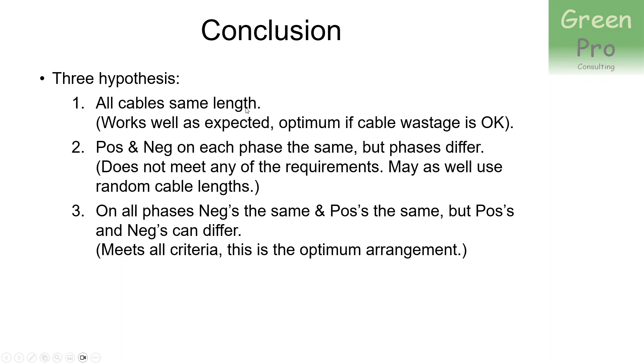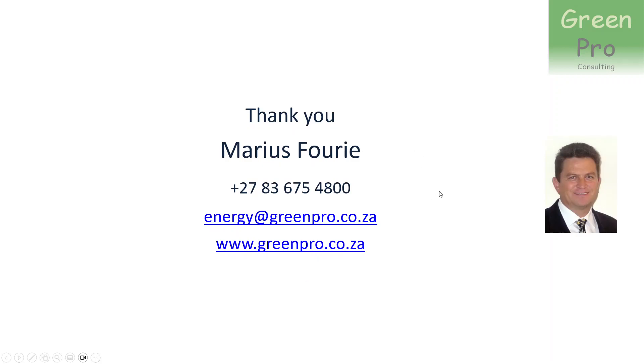In conclusion: all cables the same length works well as expected, but may waste cable and increase losses. Positive and negative the same per phase but phases differing meets none of the requirements - it's a no-no method. All negatives the same and all positives the same across phases, even if positives and negatives differ from each other, meets all criteria and in most cases will be your optimum arrangement. Thank you very much, and if you have any questions, feel free to contact me.